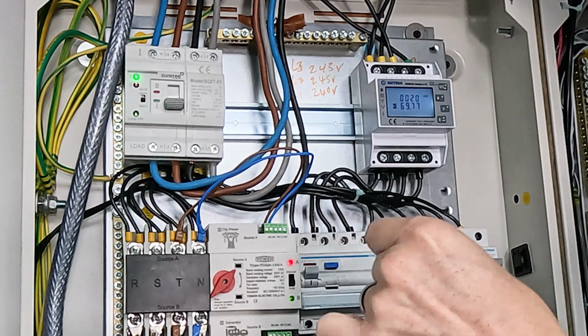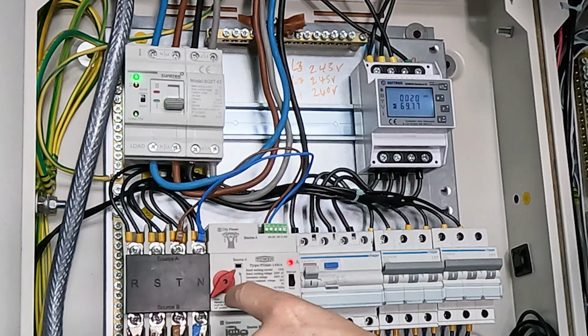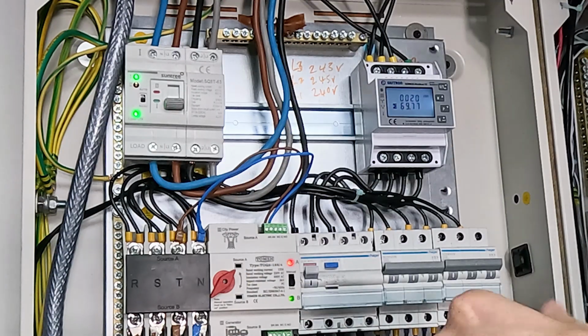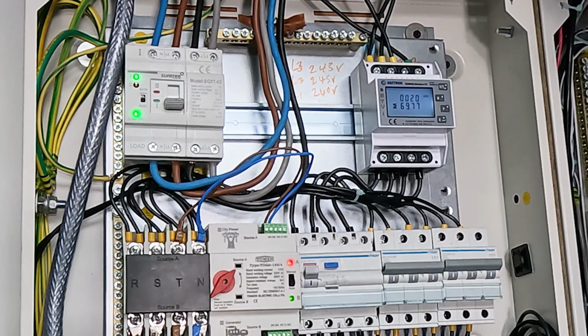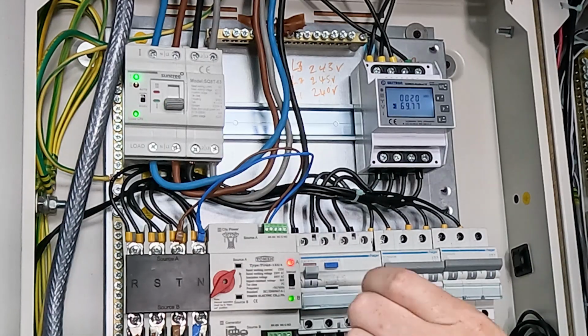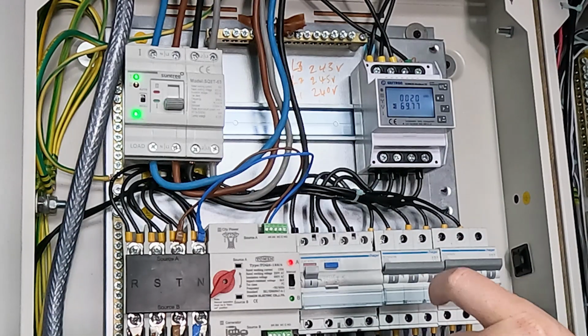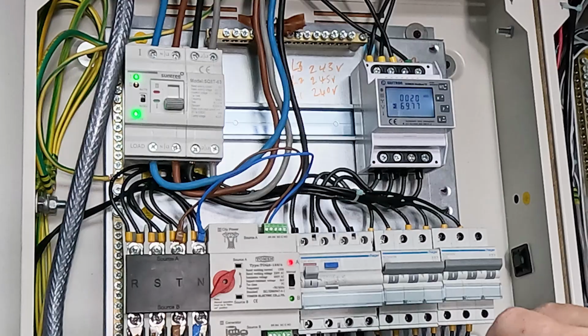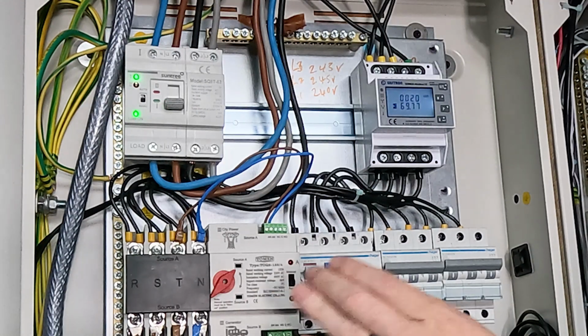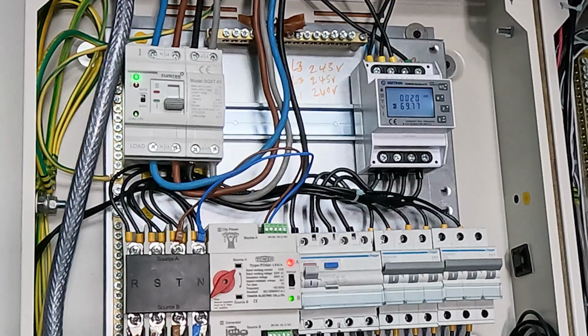Okay, so this is a transfer switch, and I've got in source A the output of my inverters. The reason why I've put my inverters on source A and not the grid is because I want the default state, when there's no voltage on anything, no voltage on grid, no voltage on the inverter, to go to source A. That is because when there is a grid outage, the inverter actually loses voltage for 20 milliseconds. And this thing will see no voltage on both for 20 milliseconds.